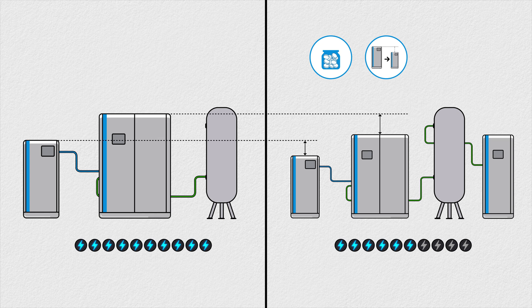That's because the generator does not need to remove that last bit of oxygen, which requires a lot more compressed air than producing lower purity nitrogen.